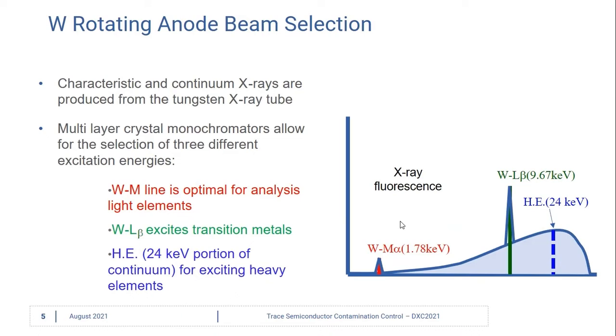The first is the tungsten M line for sodium, magnesium, and aluminum. The second is the tungsten L beta line, which excites transition metals. We also have a high energy source at 24 keV from the continuum, and this is for exciting the heavier elements.